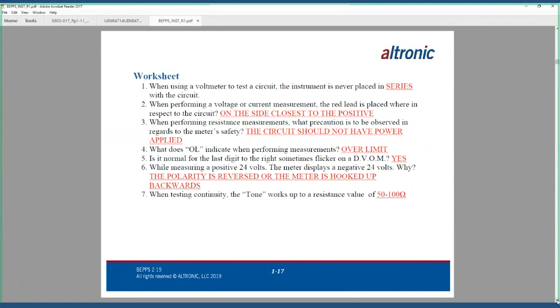Is it normal for the last digit to the right sometimes to flicker on a digital volt ohm meter? So we hadn't covered that, but yes. And the reason being, if I'm going out 3 decimal places, so let's say I'm doing 12.001 volts. Sure, there's a little bit of variance sometimes on all electrical circuits. And that's a good sign that you see that value changing maybe or flickering a little bit, because it means that the meter is actually working and collecting its samples properly.